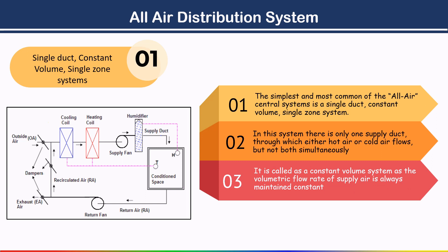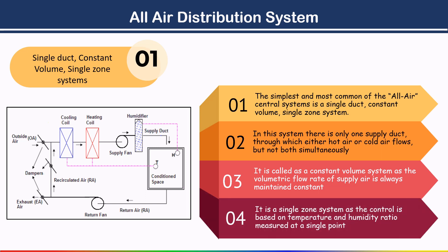This is called a constant volume system because the volumetric flow rate of supply air is always maintained constant. It is a single zone system because control is based on temperature and humidity ratio measured at a single point. As shown in the figure, outdoor air for ventilation and recirculated return air are mixed in the required proportion using dampers.